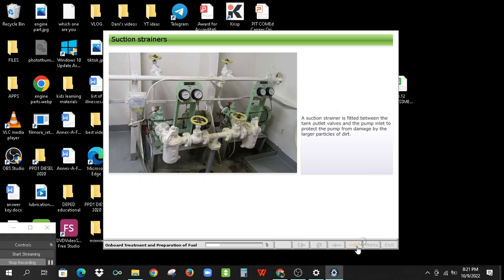A suction strainer is fitted between the tank outlet valves and the pump inlet to protect the pump from damage by the larger particles of dirt. The suction strainer usually has a coarse mesh to help ensure an acceptable flow to the pump. Only relatively large particles of dirt are removed at this stage.